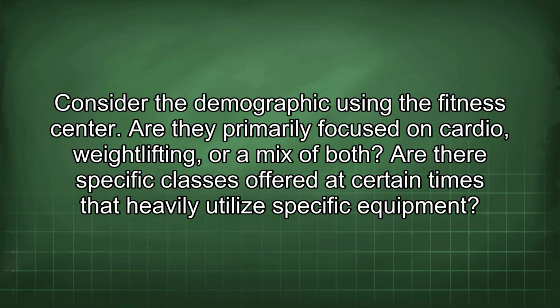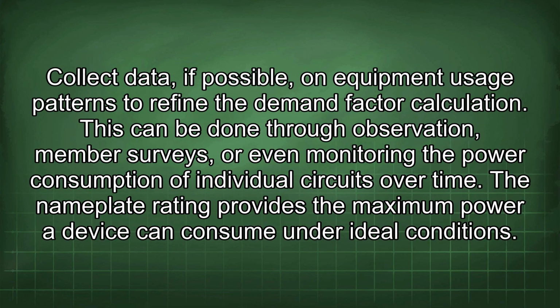Consider the demographic using the fitness center. Are they primarily focused on cardio, weightlifting, or a mix of both? Are there specific classes offered at certain times that heavily utilize specific equipment? Collect data, if possible, on equipment usage patterns to refine the demand factor calculation. This can be done through observation, member surveys, or even monitoring the power consumption of individual circuits over time.